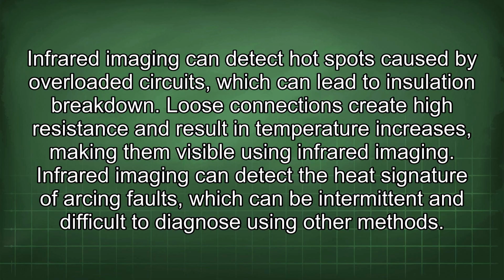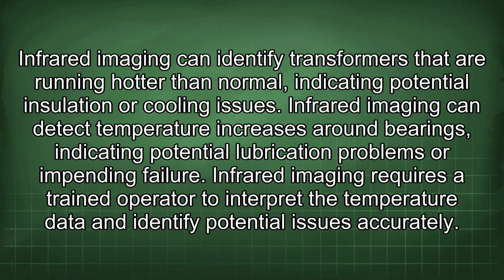Loose connections create high resistance and result in temperature increases, making them visible using infrared imaging. Infrared imaging can detect the heat signature of arcing faults, which can be intermittent and difficult to diagnose using other methods. Infrared imaging can identify transformers that are running hotter than normal, indicating potential insulation or cooling issues. Infrared imaging can detect temperature increases around bearings, indicating potential lubrication problems or impending failure.